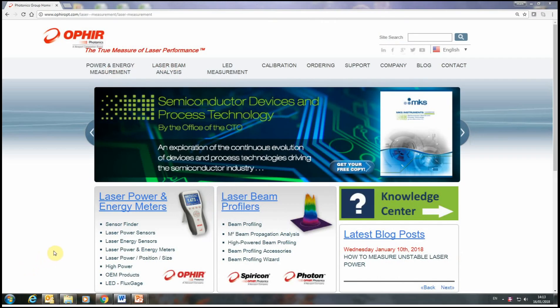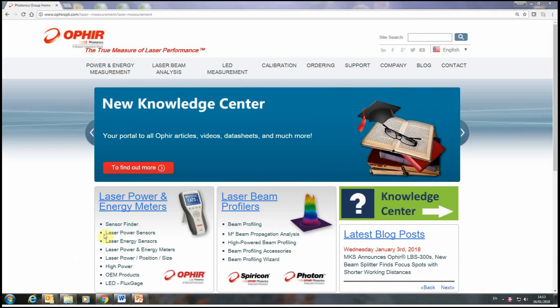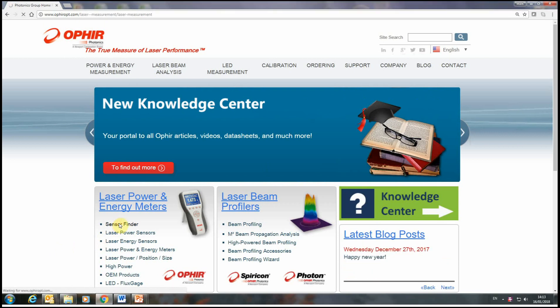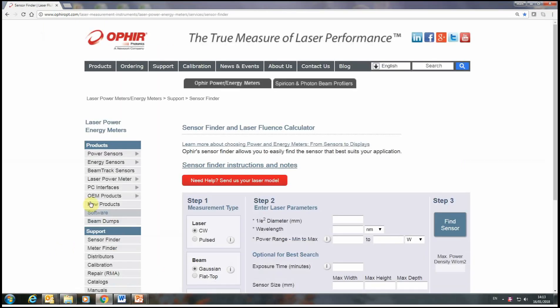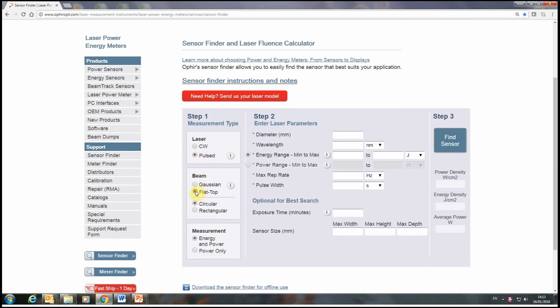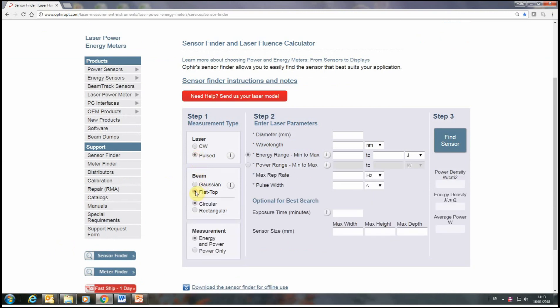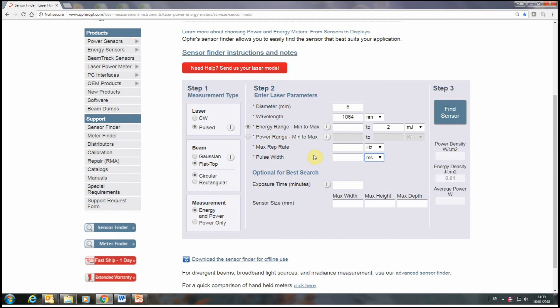In some cases, the Ophir sensor finder tool can warn you when you're heading toward that trap. That will only happen when the worst-case combination of parameters is technically impossible. For example, pulse width might be specified as up to 30 ms and pulse frequency as 10 to 200 Hz.